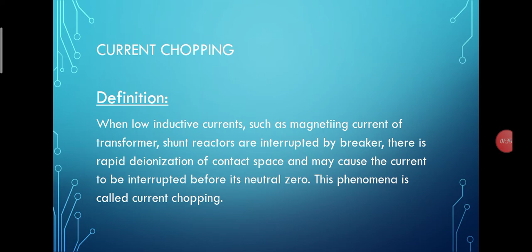The explanation of current chopping: it is a term that came into our vocabulary with the advent of vacuum switching, which was commercially started back in the 1950s. Usually, switching means in air or oil are, in terms of dielectric recovery rate, relatively slow, and as the main contacts part, the arc could go through several zero crossings before it could finally go out, and the dielectric strength across the now open gap would be strong enough to prevent a restrike, while interrupting highly inductive current like the no load current of a transformer.